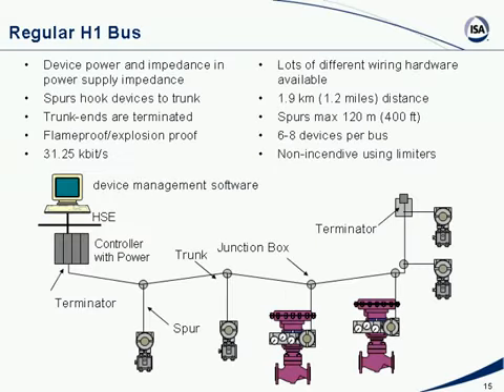Let's take a look at the design of a regular H1 bus. First of all, in the control room you have the controller that also has an H1 field bus interface card, and there is a power supply somewhere in the panel. You can't connect 24-volt DC directly to field bus. You need a so-called power conditioner in between. The reason is that the power is DC, communication is AC, and you don't want the DC bulk power supply to short circuit the AC communication. So the conditioner is really a power supply impedance.